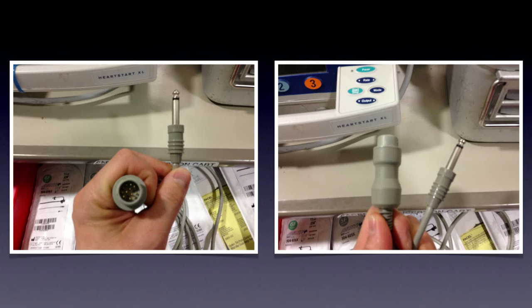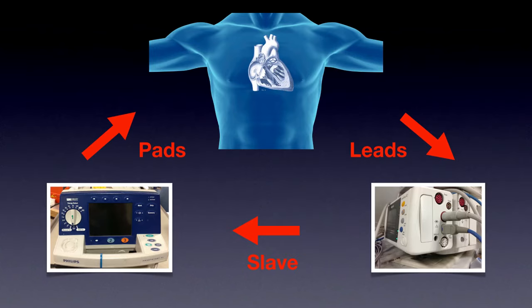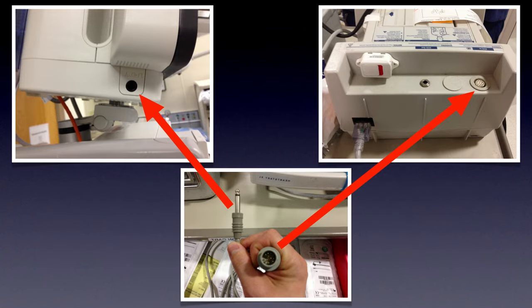If you want demand mode for a semi-conscious patient, you use a cable with a multi-pin ECG connector on one end and a stereo headphone jack on the other — the different ends tell you where each plugs in. The patient's leads go to your room monitor, the monitor slaves to the pacemaker/defibrillator via that cable, and the pacemaker connects to the patient via pads. The rhythm is sent through the leads to the monitor, slaved to the pacer, which then paces the patient through the pads.